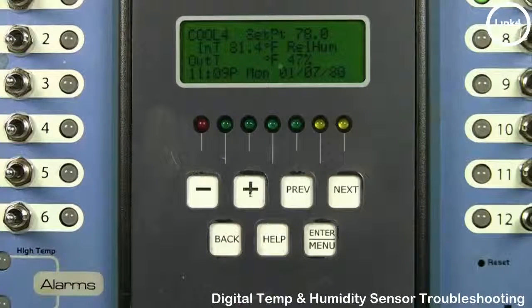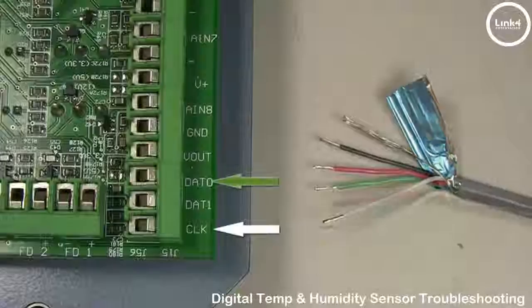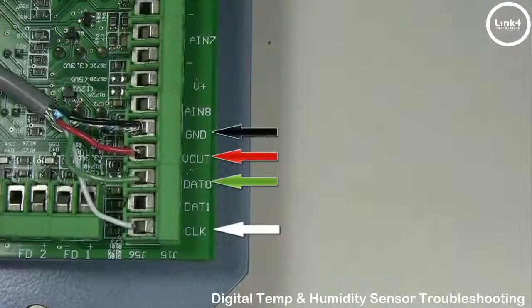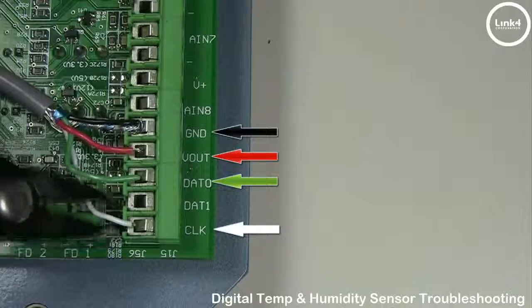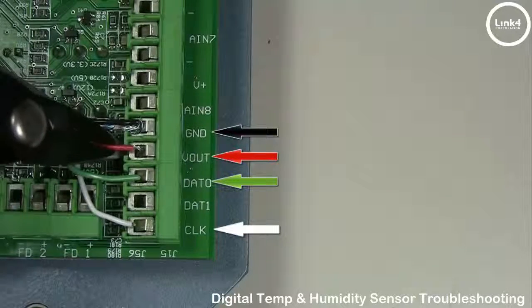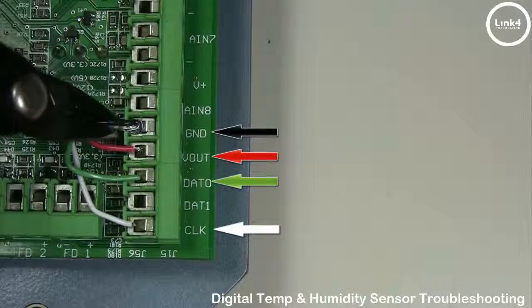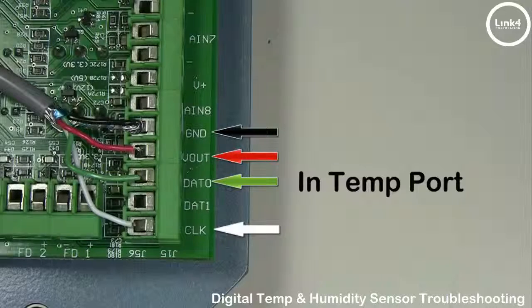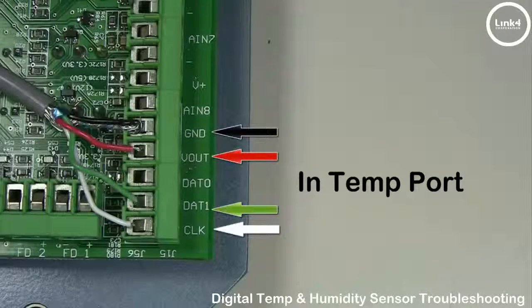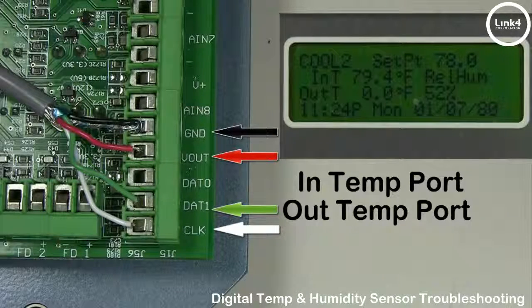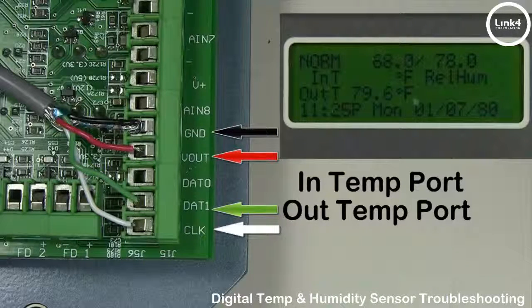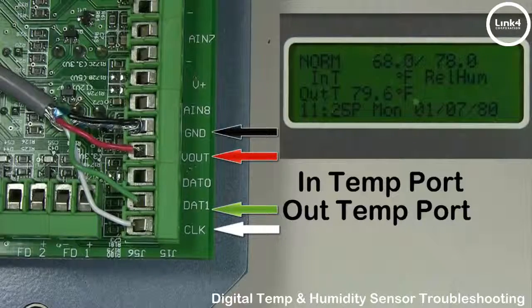Since our self-test is disabled, sensors map correctly, and there's no calibration affecting our sensor reading, let's examine the external aspects from the controller to the sensor. The first thing you want to do is inspect your sensor wiring on the relay outputs CLK, Data 0, Vout, and GND. You want to ground the shield within the four-conductor cable and check the sensor wiring to make sure that they're all snug and tight. You could also test the in-temp port by simply moving data 0 to data 1 and see if the out-temp is displayed, which will make the in-temp blank and the out-temp populated because you changed the data port.